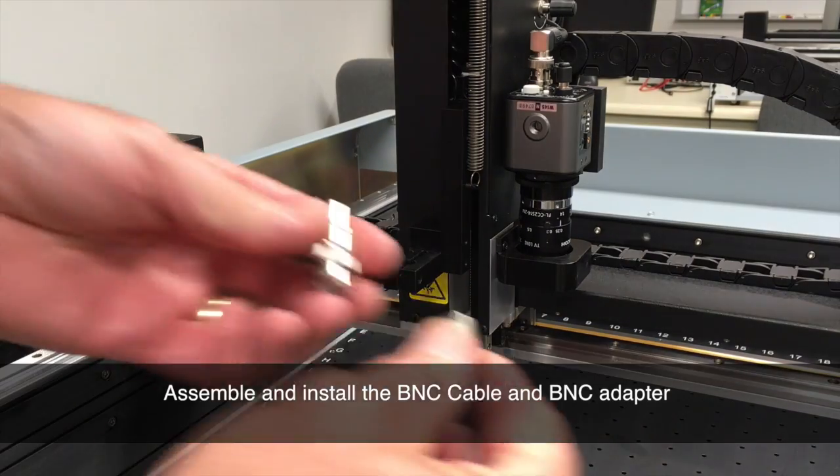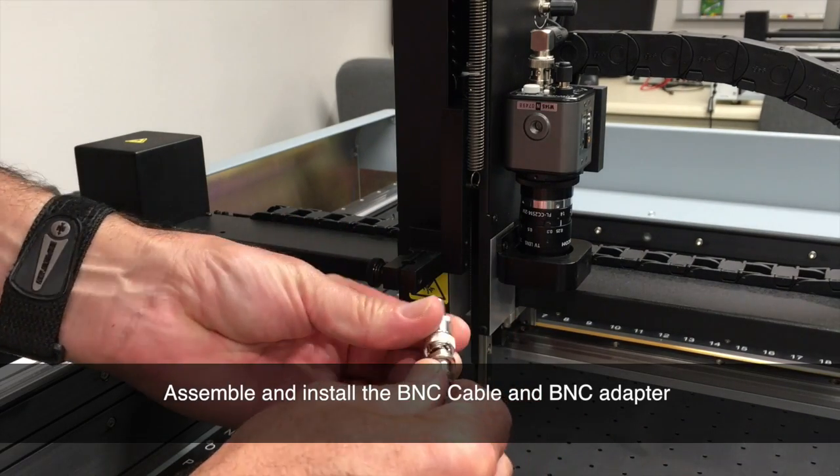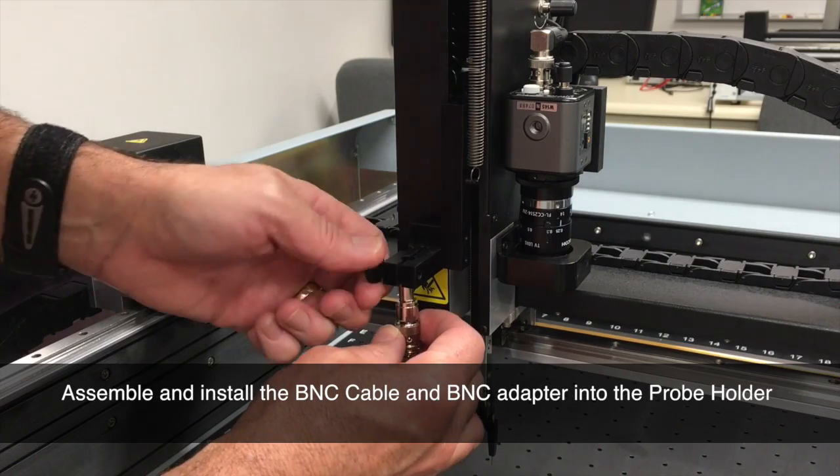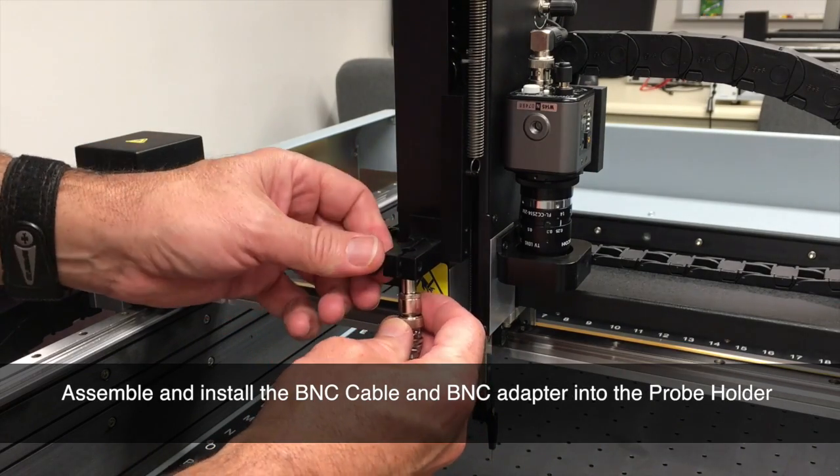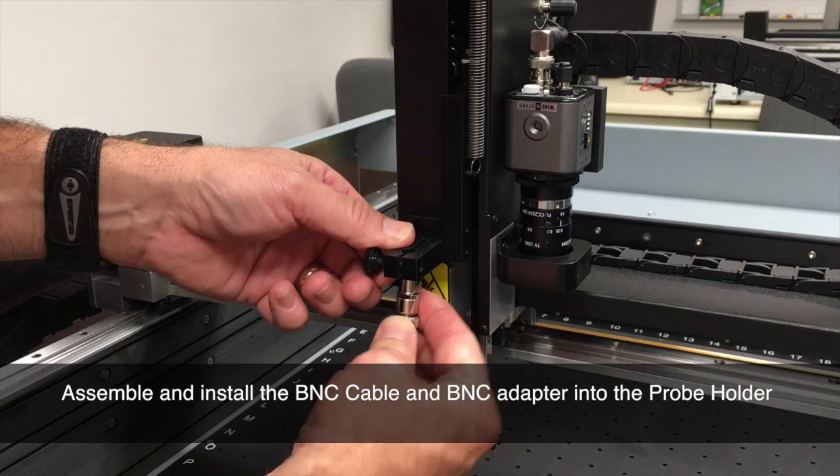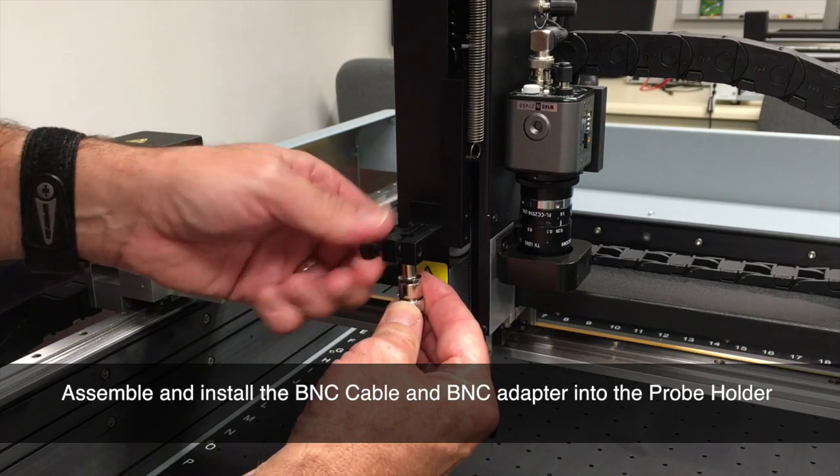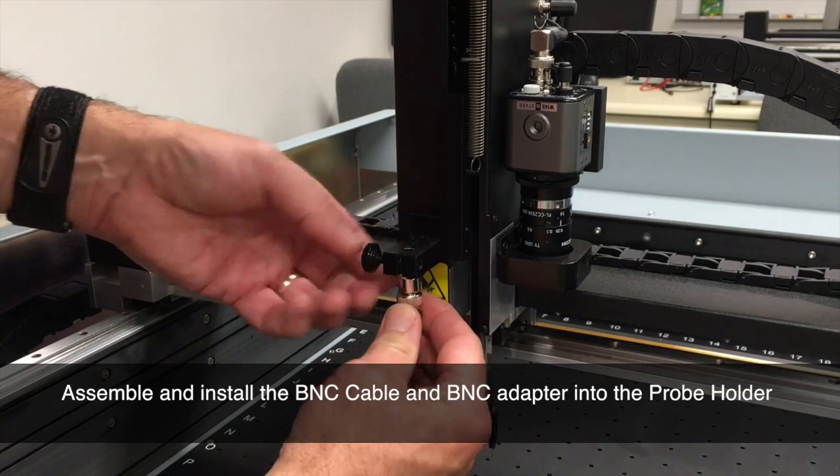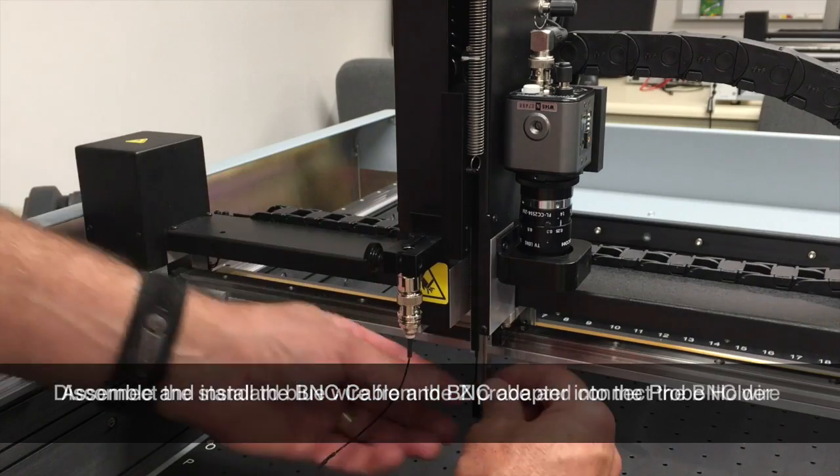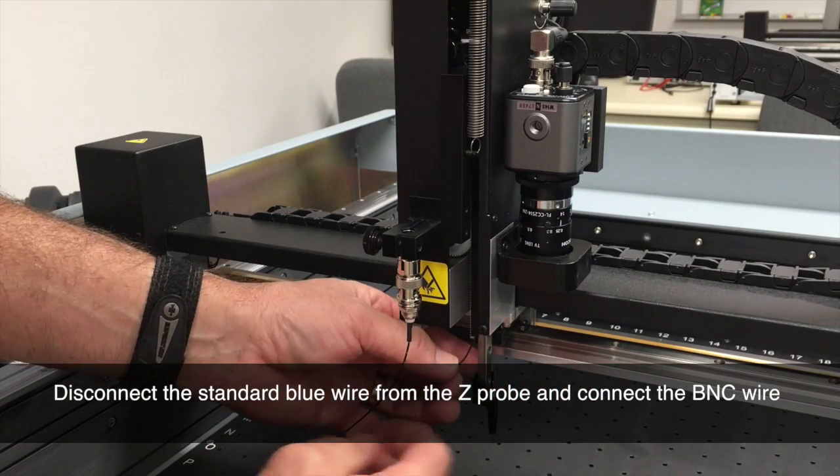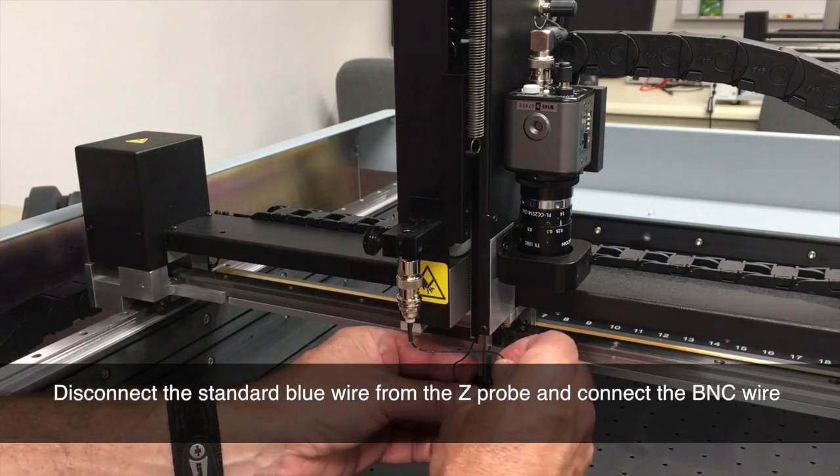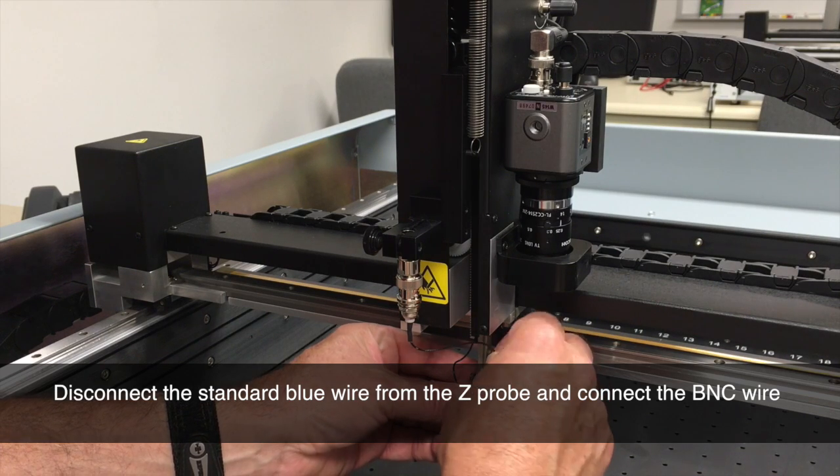Make sure they're secure. Next, assemble your BNC cable and BNC adapter. This inserts into the probe holder and has a wire that will connect down to the Z-Probe. Install that into the probe holder. Take the wire and disconnect the existing wire, the blue wire.